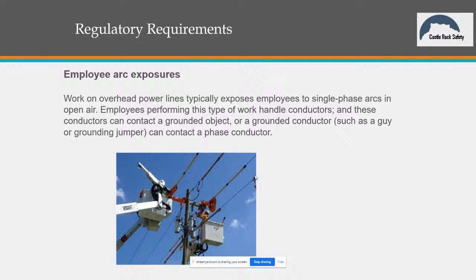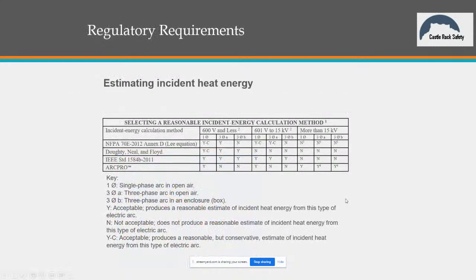Now, can you take that number and divide it by 3 to get a single phase event? No. There's the method that we use. This table indicates that they basically recognize 4 different methods for calculating arc flash or incident energy. You've got your NFPA 70E Annex D, which are the Lee equations. I think you're familiar with the Lee equations.